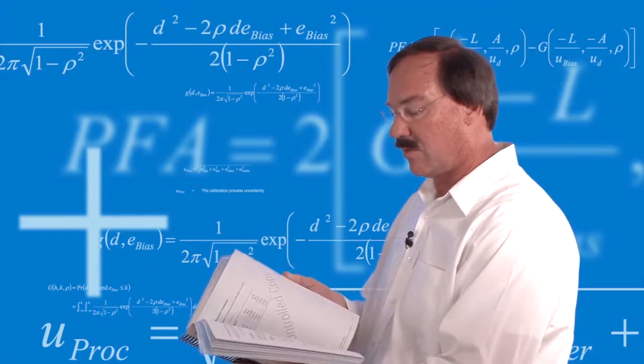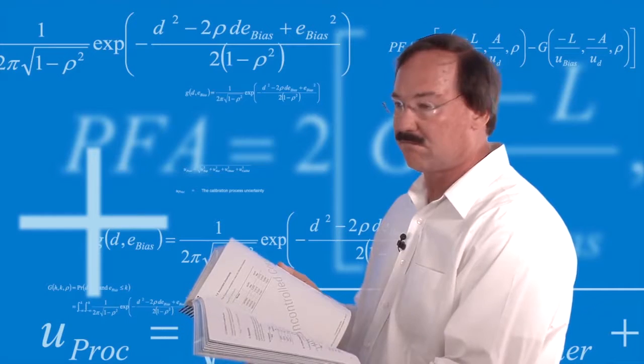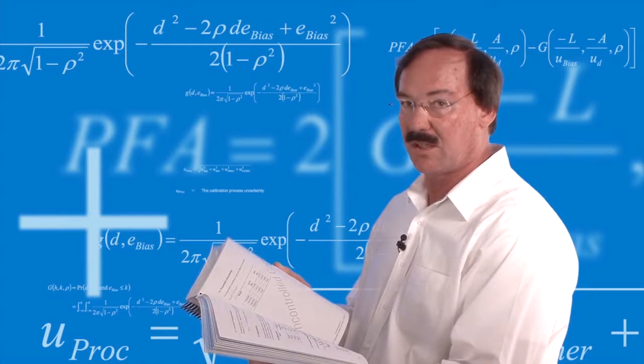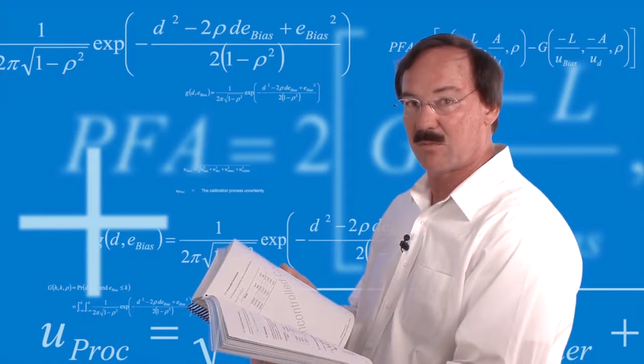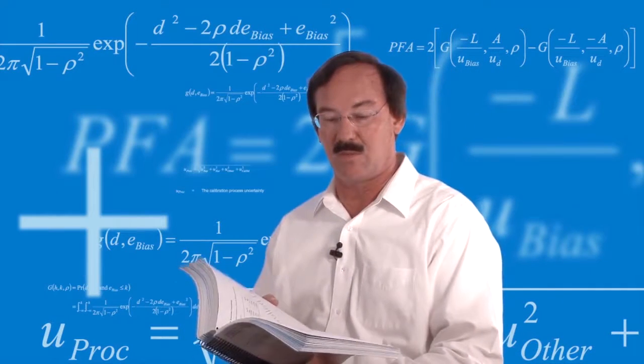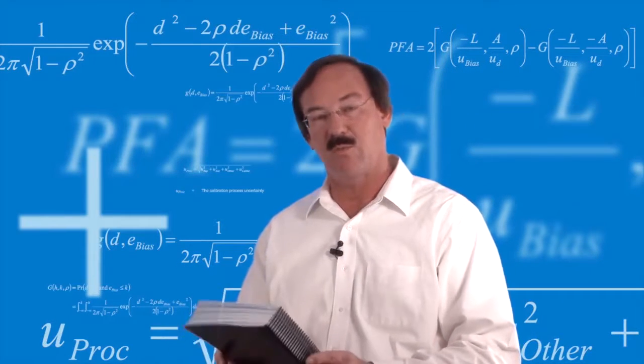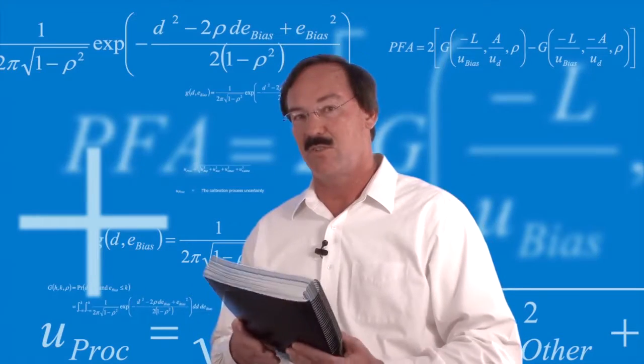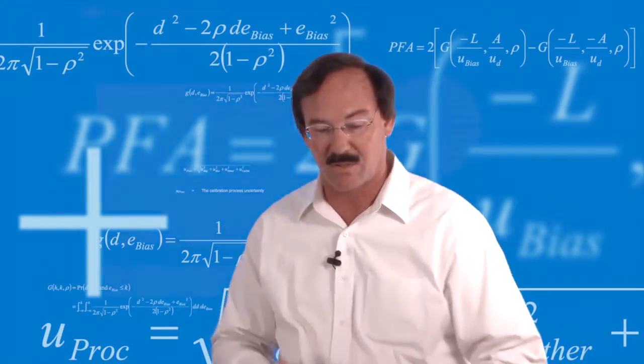So if we were to thumb through here, we would find a lot of formulas as part of the measurement uncertainty. And those are what get coded into our automated calibration software so that when we bring you measurement uncertainty in a report, this is where they're coming from.